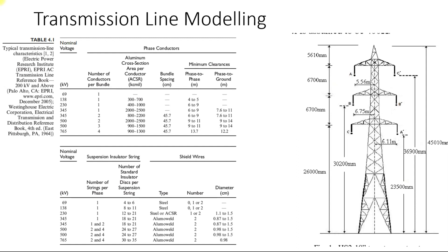In eTAP, you have two options: you can enter the passive values R, X, and B directly into the software, or you can enter the physical parameters — the tower geometry, conductor data, and ground wire data — and eTAP will automatically calculate the R, X, and B values for you. It totally depends on what data you have available.